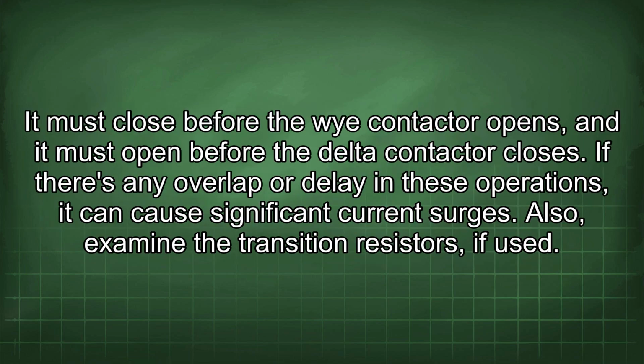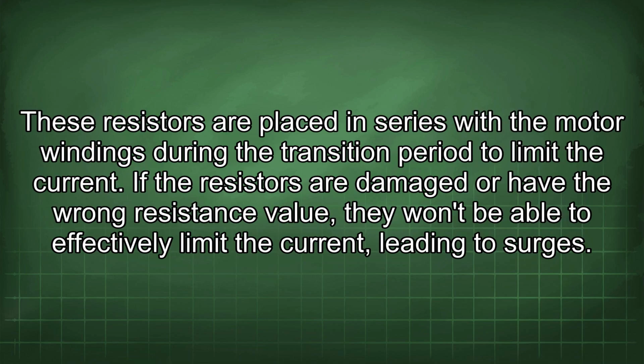It must close before the Y contactor opens, and it must open before the Delta contactor closes. If there is any overlap or delay in these operations, it can cause significant current surges. Also, examine the transition resistors if used. These resistors are placed in series with the motor windings during the transition period to limit the current. If the resistors are damaged or have the wrong resistance value, they won't be able to effectively limit the current, leading to surges.